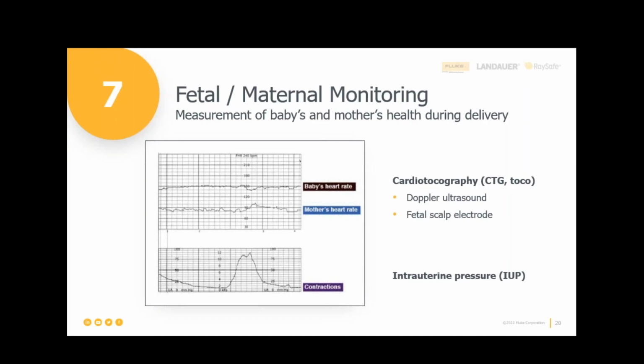Then the other way we can measure EKG and heart rate is with a scalp electrode. It's a little screw thing that actually goes in the baby's scalp for when the baby's in real trouble, and we really need a much more direct way of measuring. So make sure that you're testing that part of the system, but those are single patient use, disposable connections to the baby and the mom. The mom is going to get regular ECG electrodes and lead wires. So same problem that we have any other place with those.